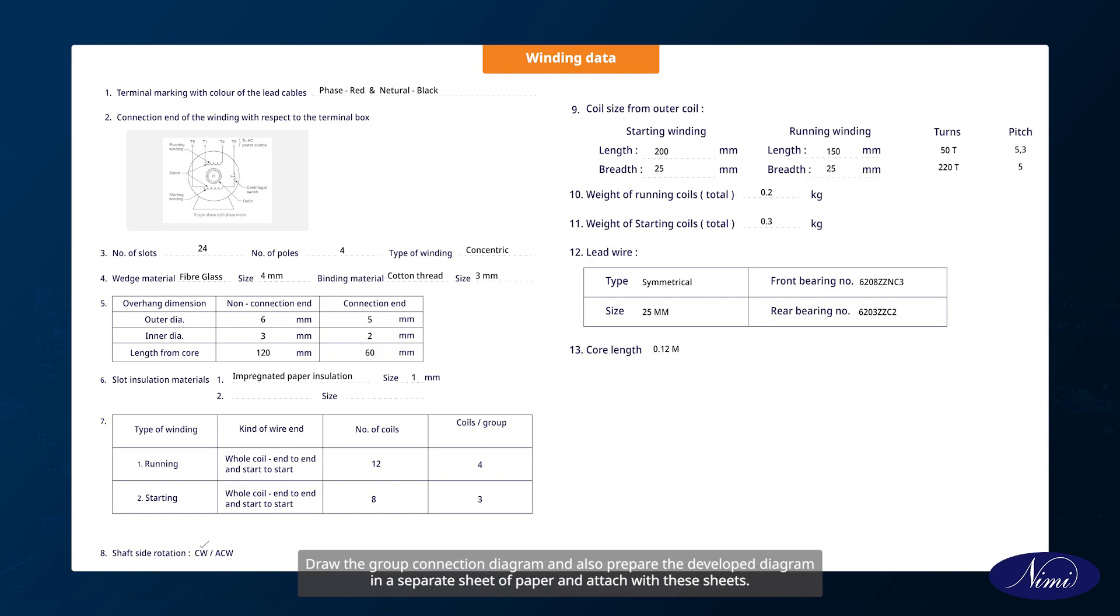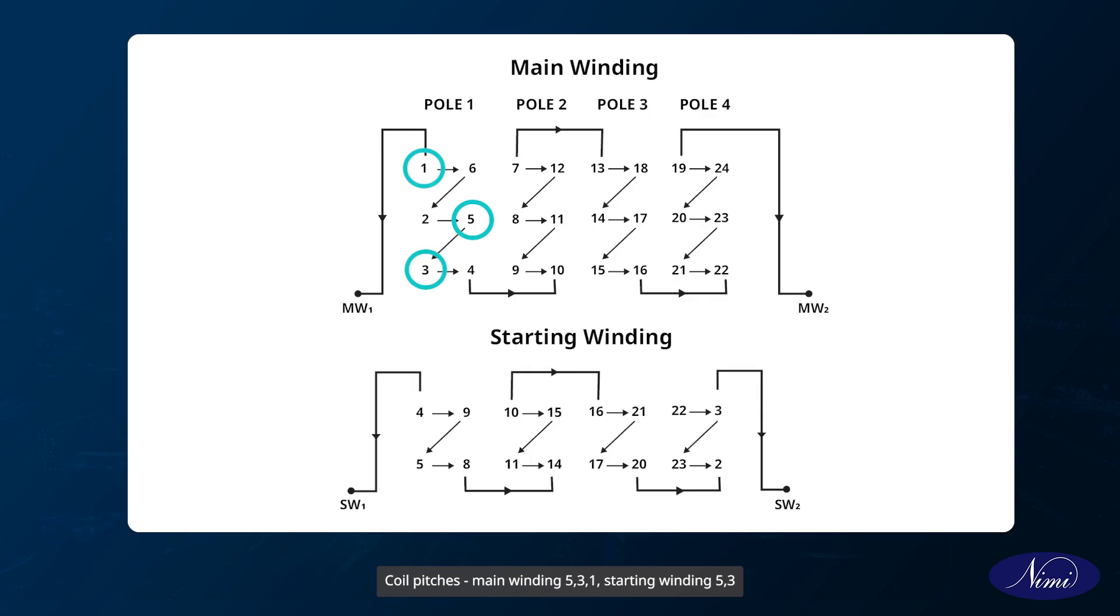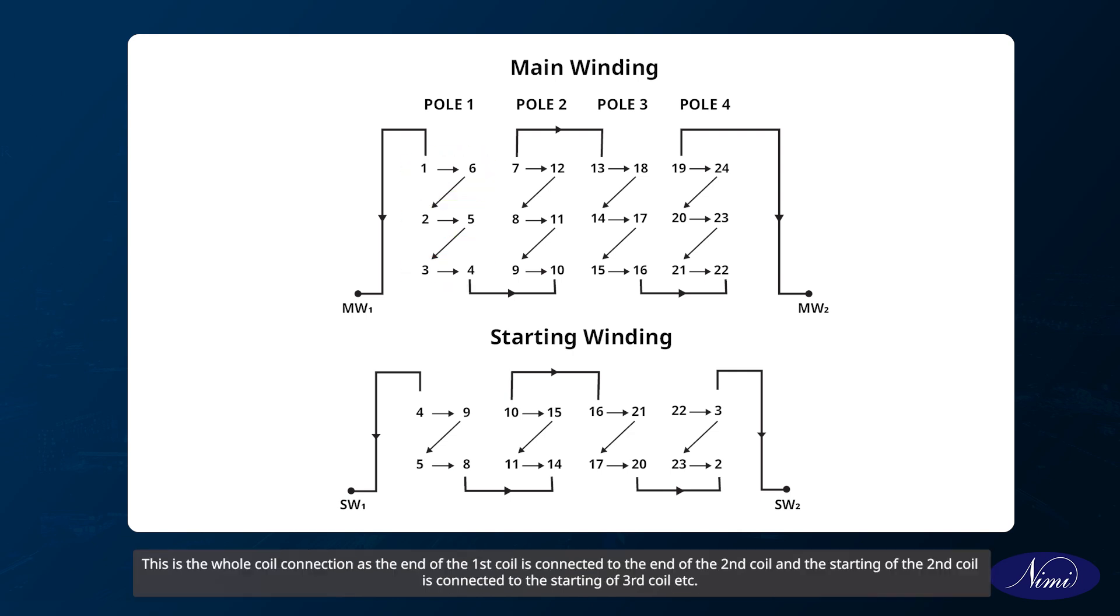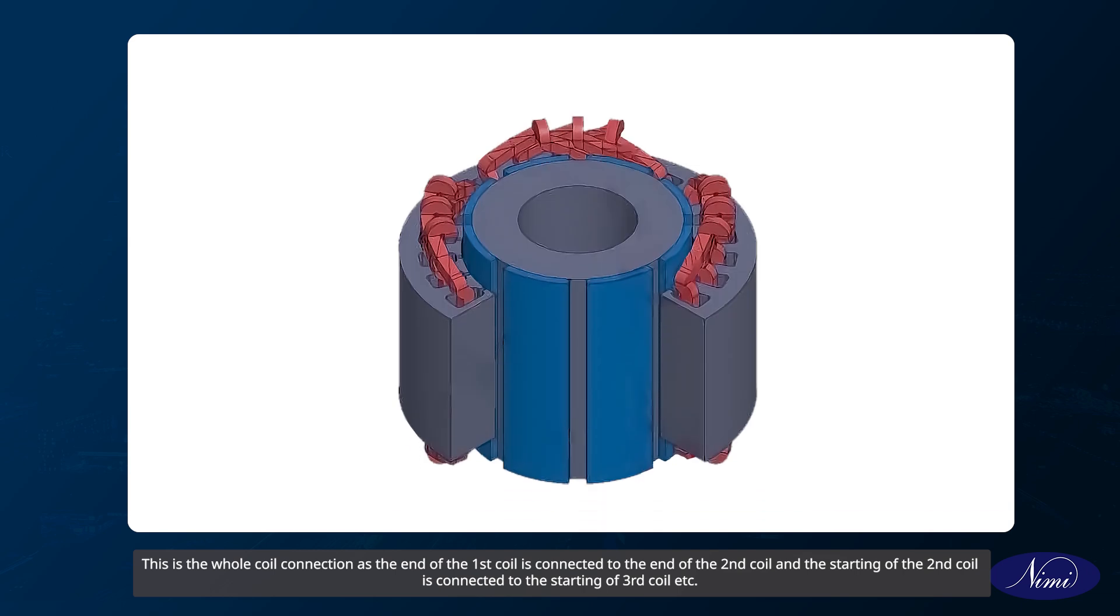Information from collected data: coil pitches main winding 5-3-1, starting winding 5-3. Coil through main winding 1 to 6, 2 to 5, 3 to 4. Starting winding 4-2-9, 5-2-8. This is the whole coil connection as the end of the first coil is connected to the end of the second coil and the starting of the second coil is connected to the starting of third coil.